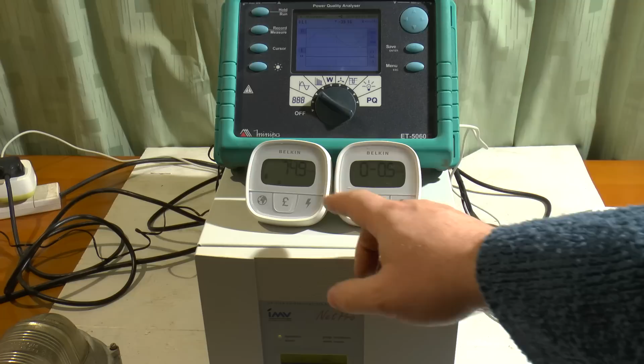Efficiency, because it's an online UPS, is something I can check, because we're actually checking the power flowing into the system and flowing back out. It's not a line interactive UPS. That is going to make a difference. So here's a 100 watt light bulb. See, 100 watts out. Although interestingly, the unit thinks that light bulb is drawing 73 watts and 102 VA on the display. And for that 100 watts out, we've got 180 coming in.